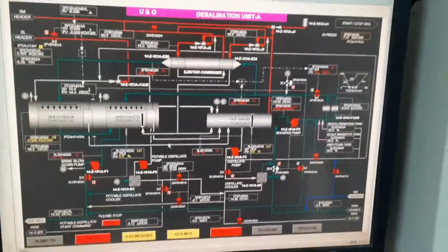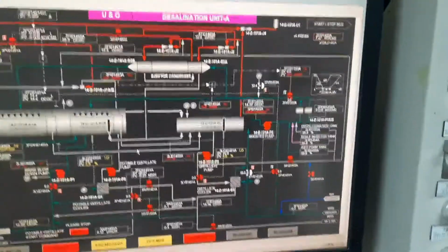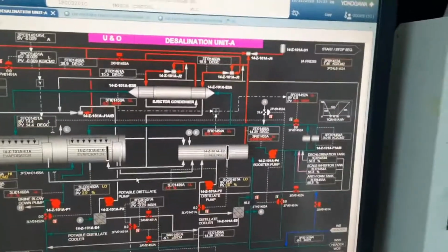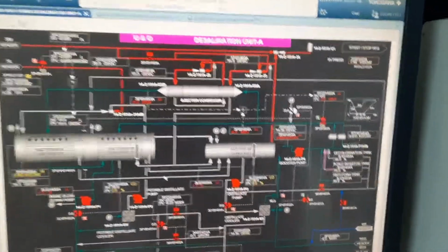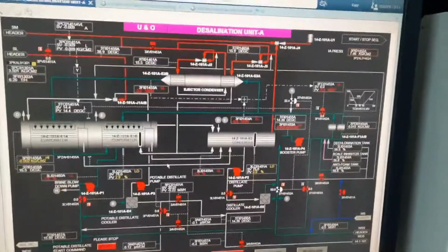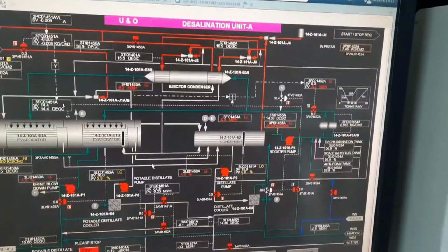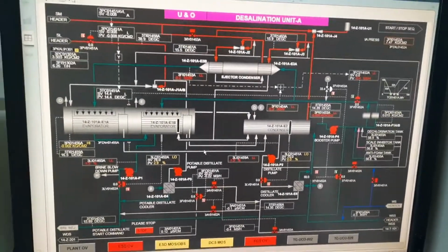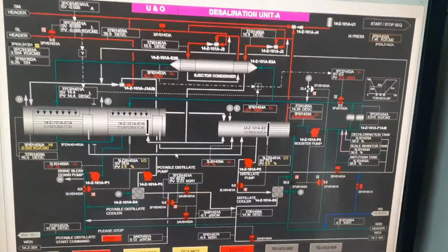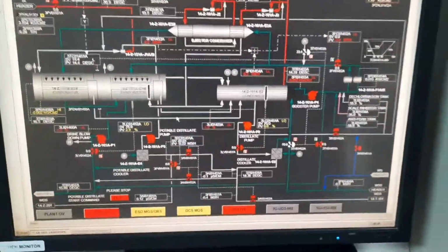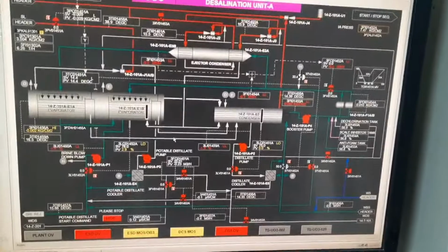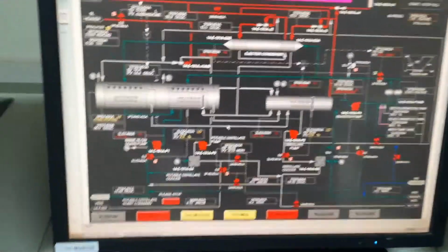After that, vacuum break and drain, to confirm that no gases remain on this side. These gases are harmful for the body, and most harmful for the eyes. If anyone enters this evaporator with the gas, they will have eye problems. Anyone affected by these gases needs to wash both eyes with service water for at least 15 minutes.